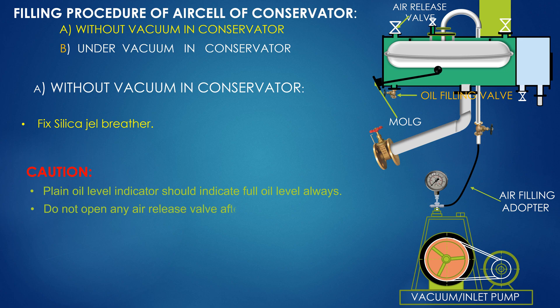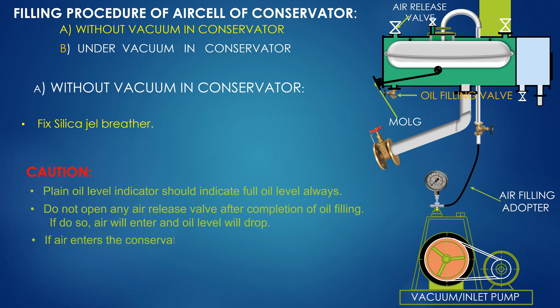Fix the silica gel breather. Caution: the plain oil level indicator should always indicate full oil level. Do not open any air release valve after completion of oil filling; if you do so, air will enter and the oil level will drop. If air enters the conservator, it can be seen as a fall in oil level in the plain oil level indicator.